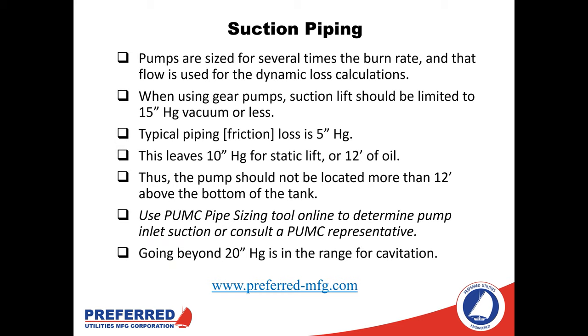Taking a look at piping now — we have the amount of fuel in our system and how fast it's moving, so we can start sizing piping and valves. Looking at our system overview, even though the piping between the main tank and the transfer pump set may be the shortest run physically, it is going to be 90% of the consideration for designing and troubleshooting in the field. That's because with positive displacement pumps that are self-priming, that section of piping will generally be under a vacuum, whereas the rest of the system will be under positive pressure. Something under a vacuum can pose a lot of issues.